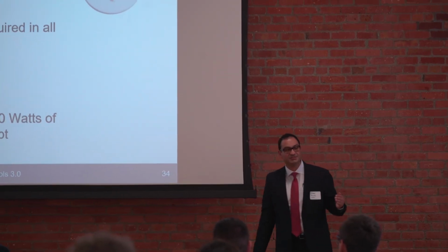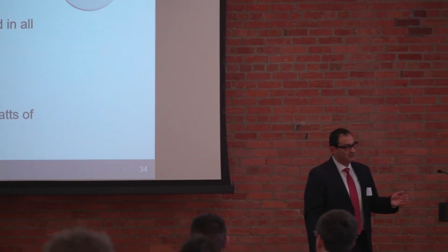Off is now a new step. So when there's enough daylight in the room, the lights have to automatically go to off. And daylight zones with 150 watts or less of lighting in the whole space are exempt.